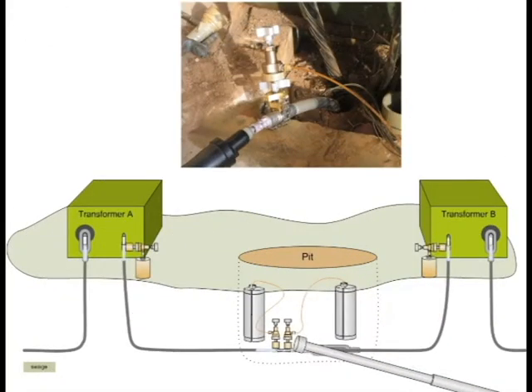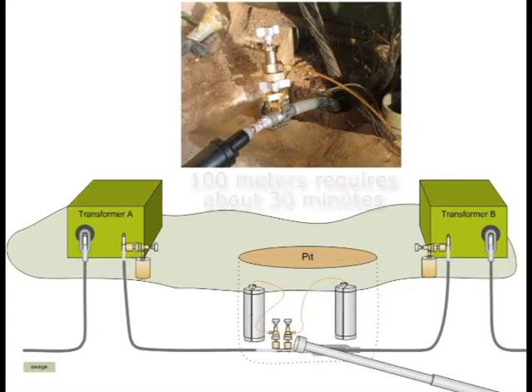Injection tools are installed on each IA. Feed and receiving bottles are placed on the end of each cable sub-segment. Fluid is injected at moderate pressure. For 100 metres, or 328 feet, of a typical 19-strand cable, the injection takes about 30 minutes. When the injection is complete, the moderate injection pressure is sustained as the IAs are plugged.